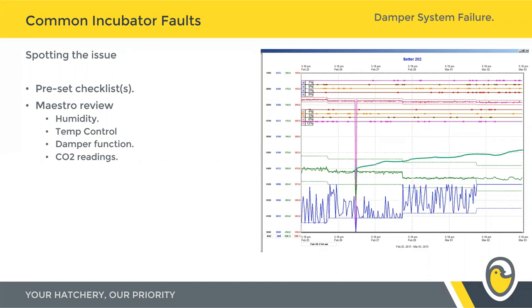If you've got a damper on your machine which is artificially low — lower than expected — you'll see a general upward trend in your humidity level inside the machine. On this particular graph, the humidity level is shown in green and the damper position in blue. It looks like the damper is modulating correctly, but the humidity level is slowly creeping up, which to me is indicative of a damper failure that's closed too low. The counterpoint would be humidity creeping downwards — the opposite, where the damper is stuck open and we're over-ventilating the incubator.